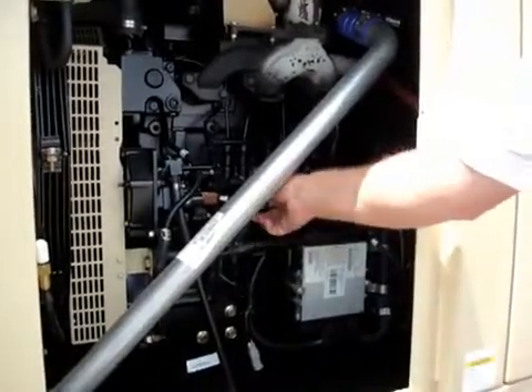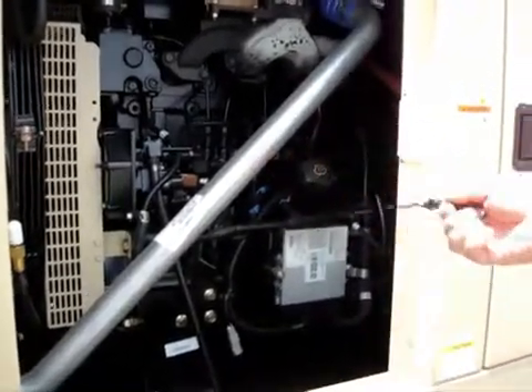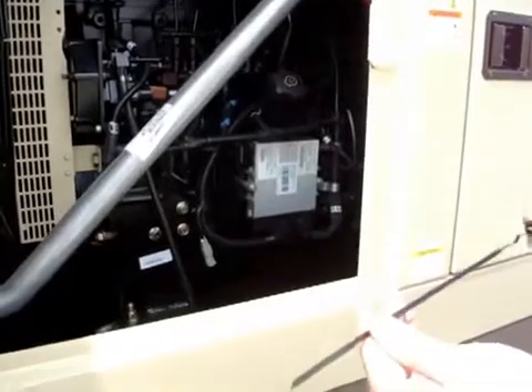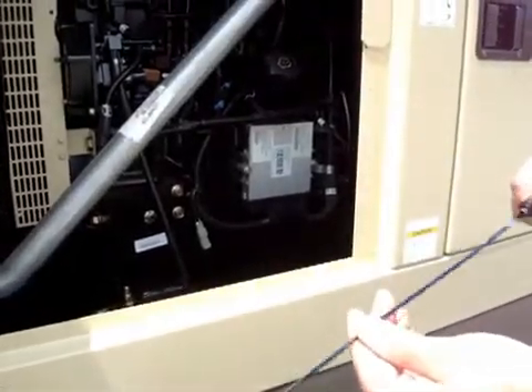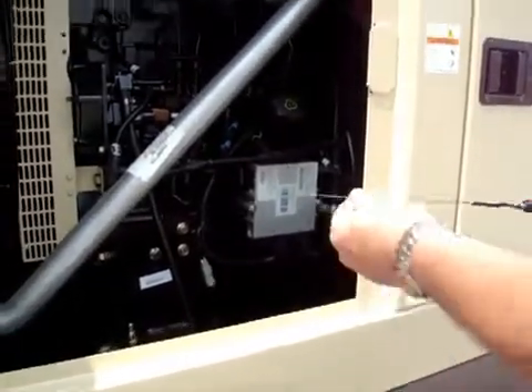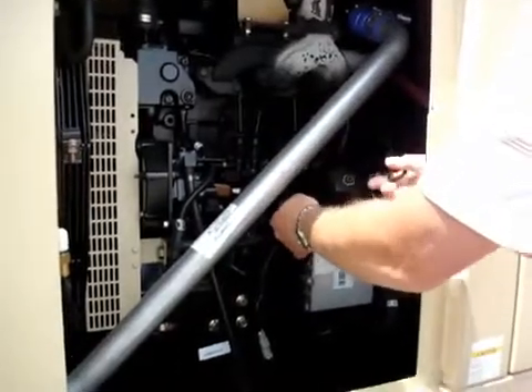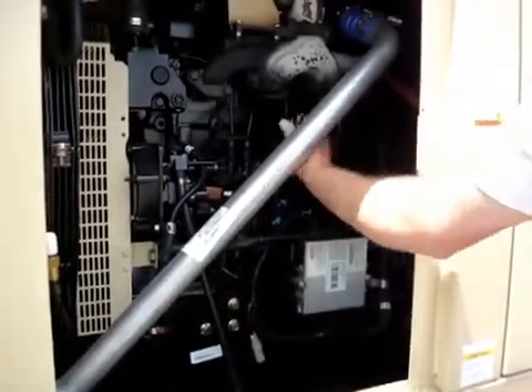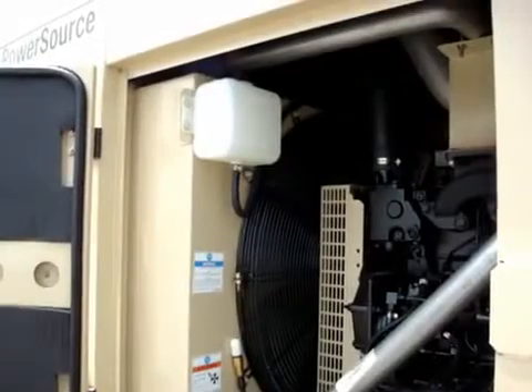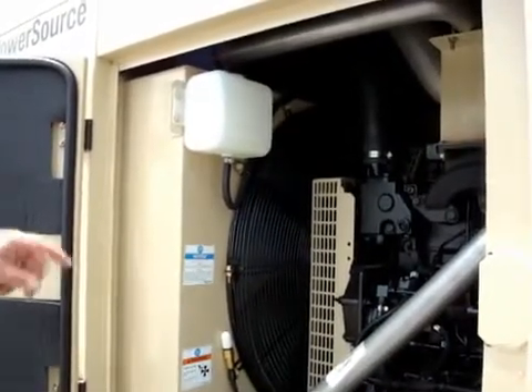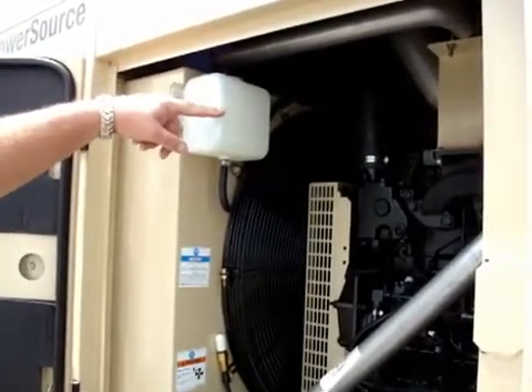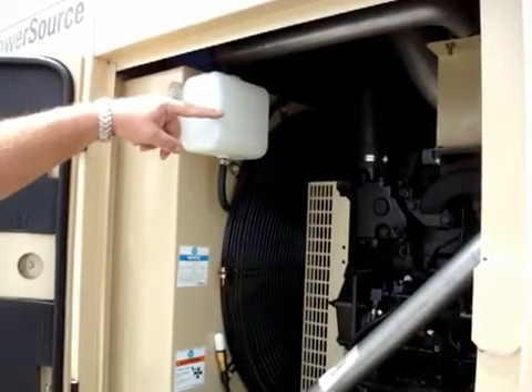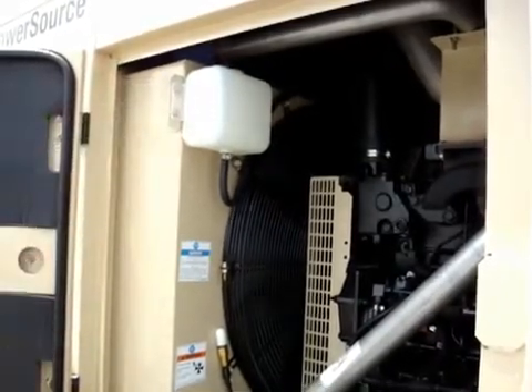Okay, first check will be the oil level. Remove the dipstick and we'll check the level to make sure it's within the hashed mark. Second check will be for radiator water level. We'll verify we have a level in the overflow reservoir right here, somewhere between the cool level and the hot level.